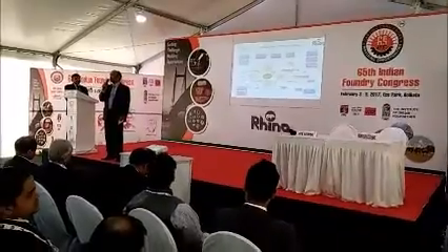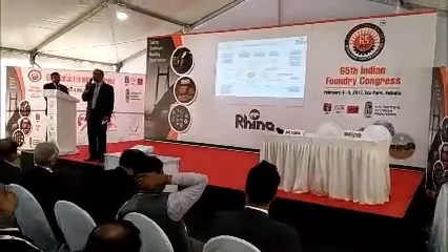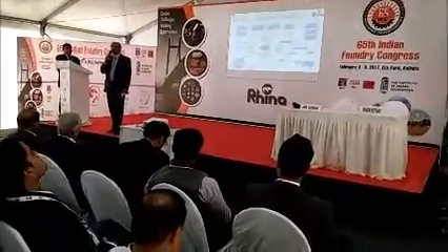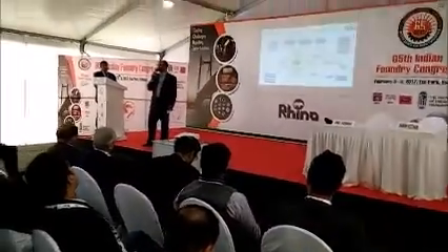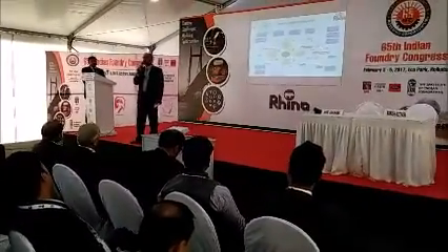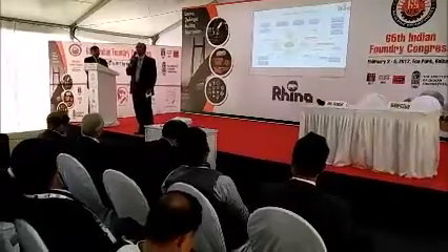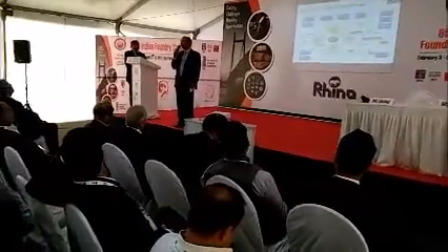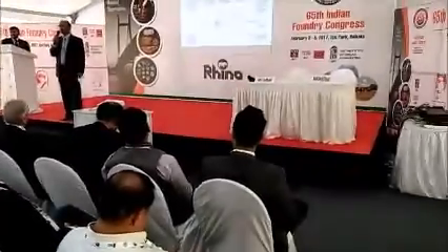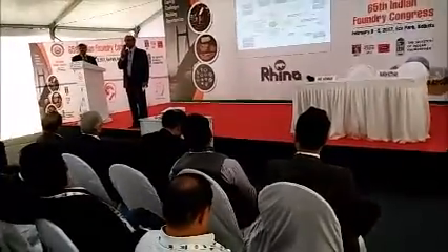What is the maximum consumption, minimum consumption, what is power factor, KVA, and if these energy meters are connected to the transformer also, there you can see the losses of the transformer. Normally no one is worried about transformer losses. Transformer manufacturer says about 2%, but it keeps on increasing. So transformer analysis can be done on losses, and you can decide the preventive maintenance schedule of the transformer. So all these small factors save your money and it can predict maintenance.